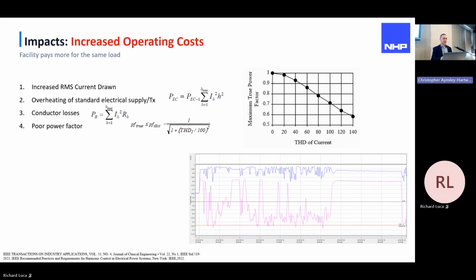Poor power factor. You can see straight away, true power factor and displacement power factor at 50 hertz can be equal if there's zero harmonics in the system. But the blue waveform down the bottom, we see a displacement power factor of roughly 0.96. And the purple waveform, that's our true power factor with harmonics in the system. So there's a differentiation there. With harmonics, you get a considerably lower power factor in the system. And that's creating a lot of inefficiencies.